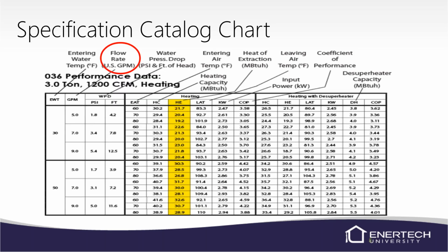Flow rate. When you pull up this manual, don't just say, well, I should be moving 5 GPM, so we're going to choose 5 GPM. One thing that's really important about this manual, we've got to have the manual because we have to compare the pressure drop that we get with our pressure gauge to the chart. And that will tell us the amount of GPM that the unit is running. I don't have a mathematical calculation to where I can just go, hey, I've got a 2-pound pressure drop at 50 degrees. Is there a calculation that tells me what that GPM is? The answer is no. Engineers figured that out in the lab. So that's why it's so important to have this manual.